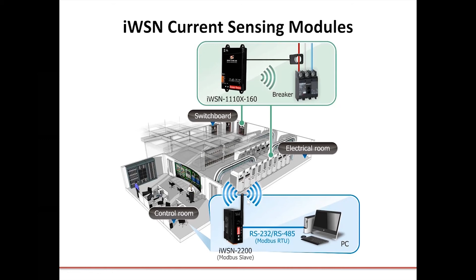Here's a quick application example of the IWSN sensor module in an electrical room, attached directly to the breaker and monitoring power consumption there. Again, it charges itself inductively through the CT, though external DC power can also be provided if needed—but the key feature is the inductive charging. It takes the power measurement and sends it to the IWSN 2200 data concentrator, which communicates over RS-232 or RS-485 using Modbus RTU to your PC, SCADA system, or building automation system.